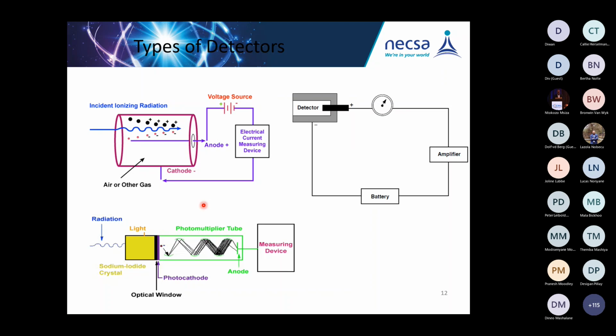This is the type of the detectors, what you will see inside your instrument. I also indicate that for the detector, you have only 3 components. You have the power supply, which is the voltage, and you also have the cathode and the anode. When the incident ionizing radiation enters this, this is how you see it, and then you get the readout, which gives you this process. It is happening inside the gas detector, and this process is happening in the Geiger-Müller tube, because the Geiger-Müller tube doesn't have the P10 gas.